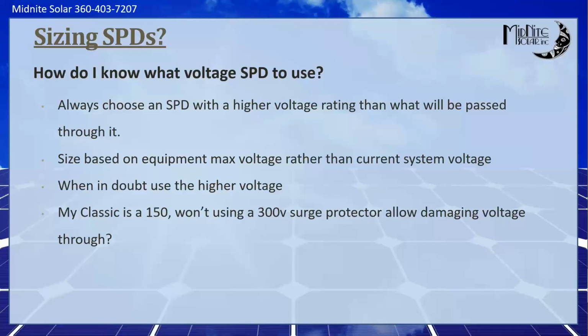I always recommend sizing the SPDs, as I do all the equipment in the system, on the device. And what I mean by that is, if we're putting in a Classic 250, I'm putting in an SPD 300 to stay at the right voltage. I'm putting in the 300 volt breaker to keep at the right voltage. Even if I'm doing 100 volts on the PV array, I'm still going to put 300 volt equipment in so that if I ever expand, I don't get bit by that in the future.